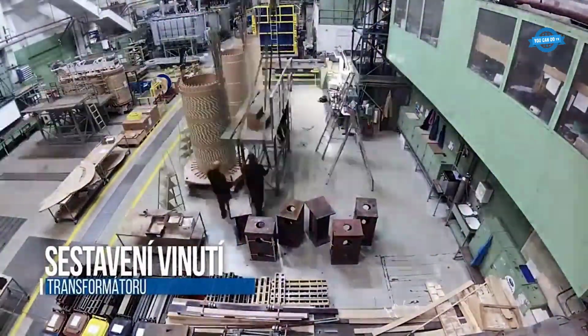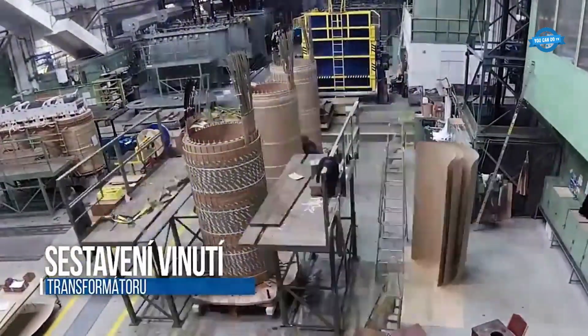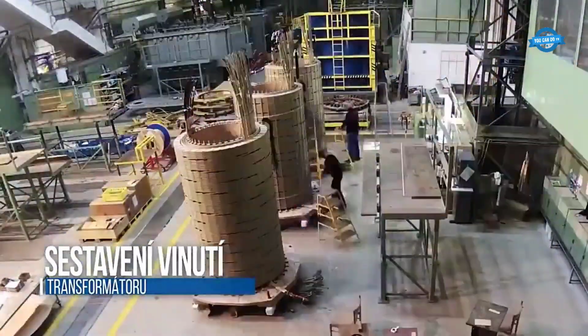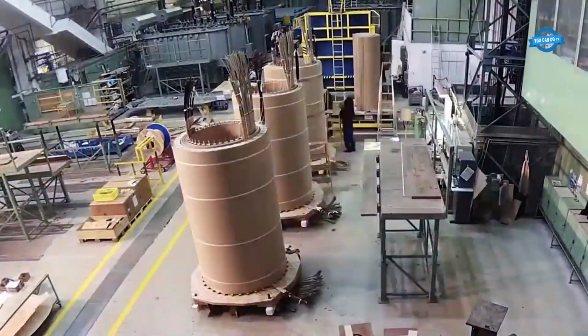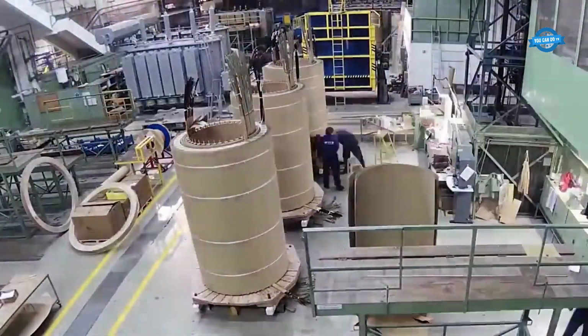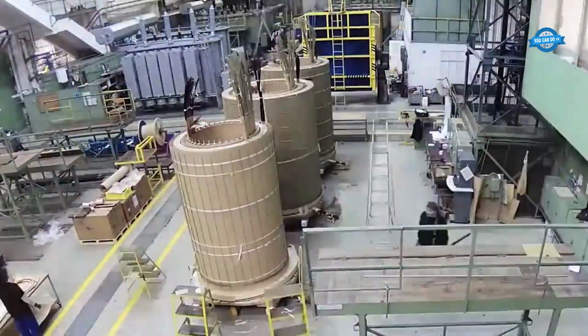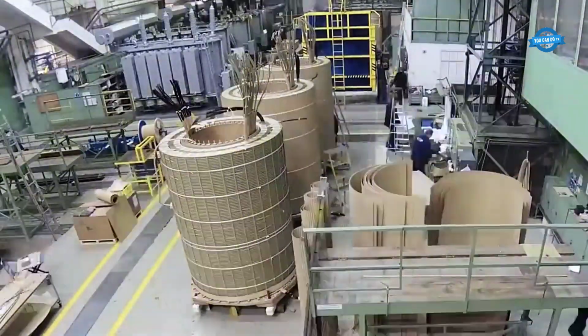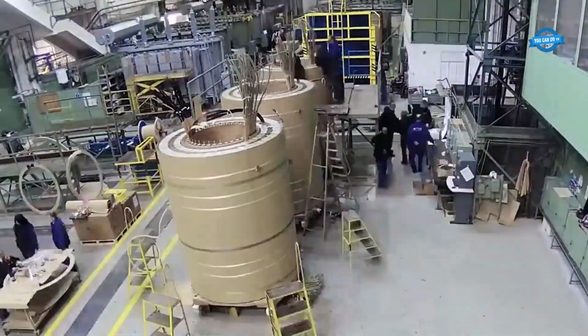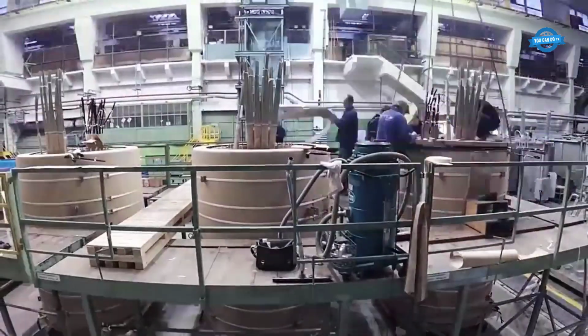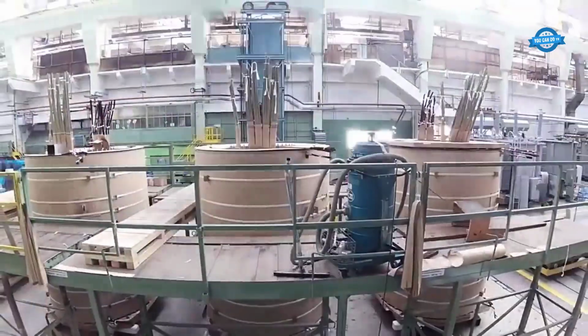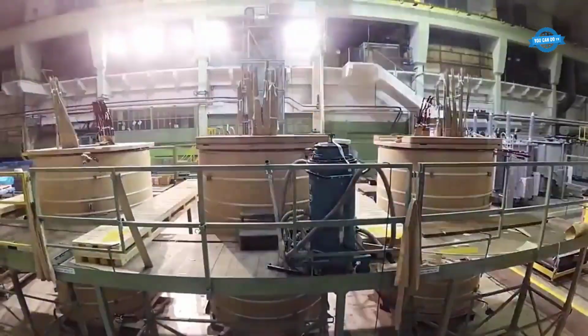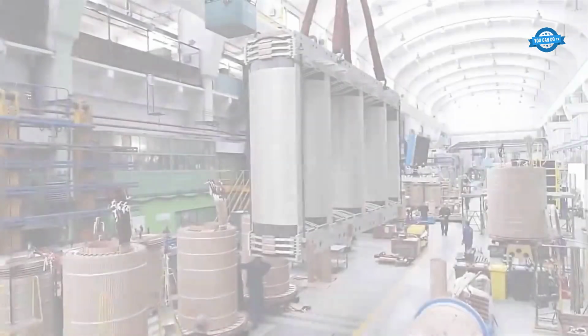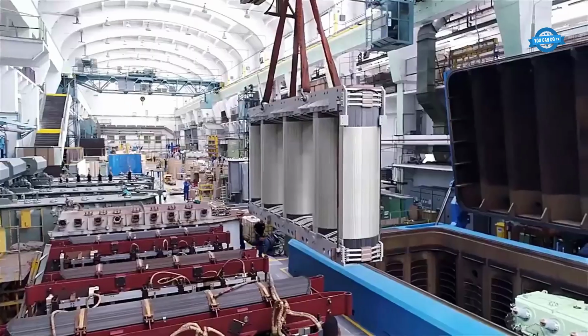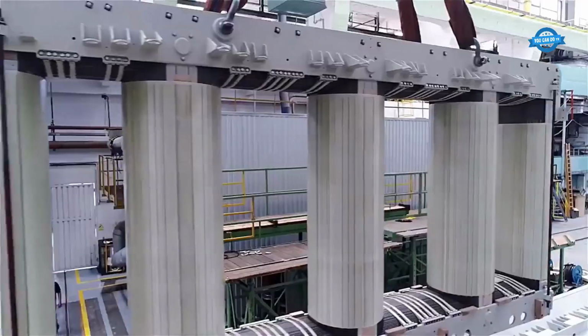Coil design and quality are keys to transformer efficiency and longevity. Thermally upgraded paper should be used for the longest insulation life. Coils are assembled with the best insulating materials and are adequately clamped.